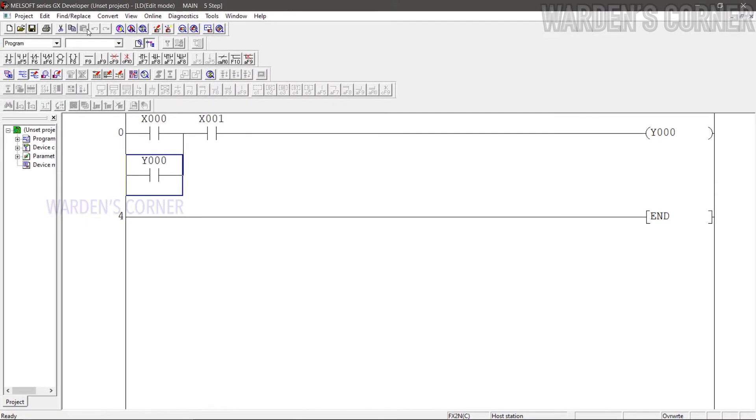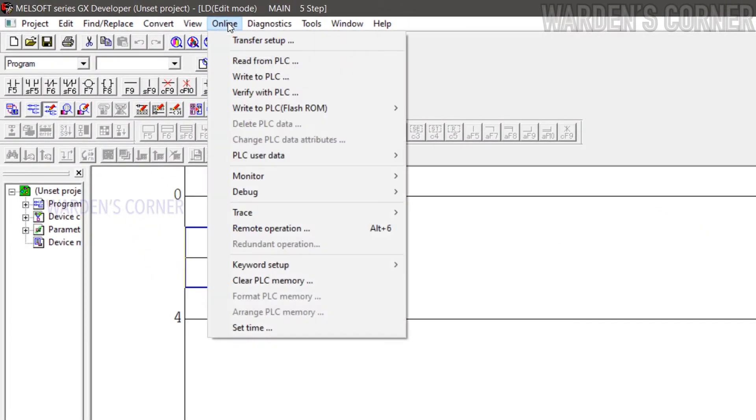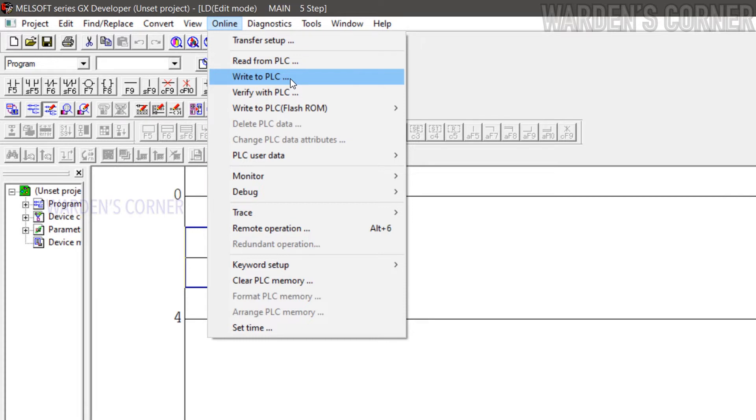Next, transfer the logic program to the PLC unit. Go to Menu, select Online, and click Write to PLC. This process is also known as downloading. For your information, Read from PLC is a process of transferring of logic programs from PLC to the computer and also known as uploading. Click the video link above for a more detailed explanation of PLC's downloading slash uploading processes.